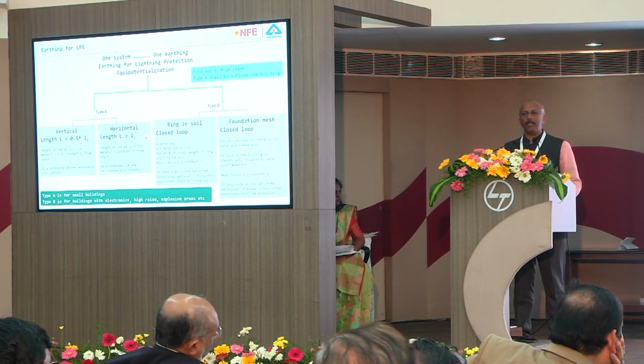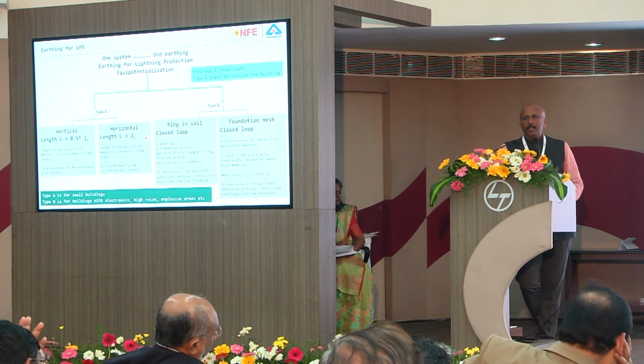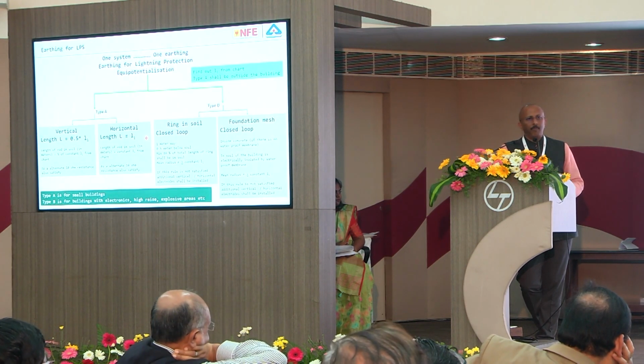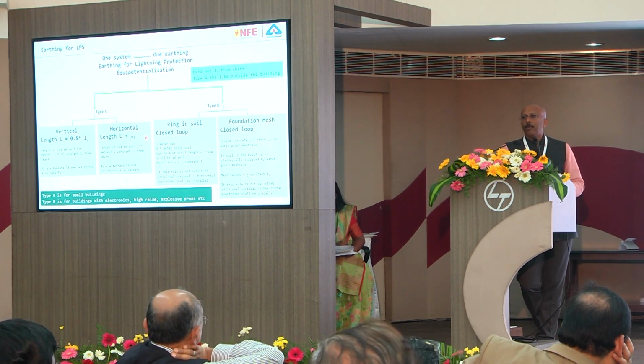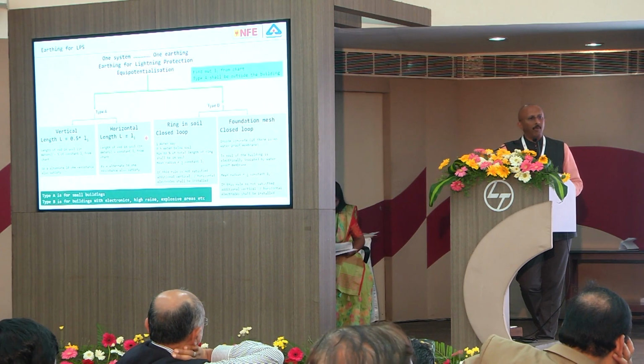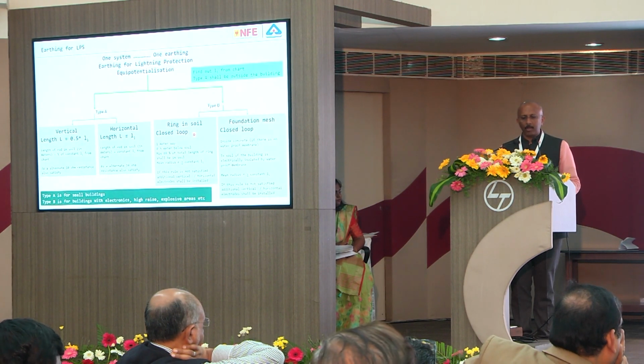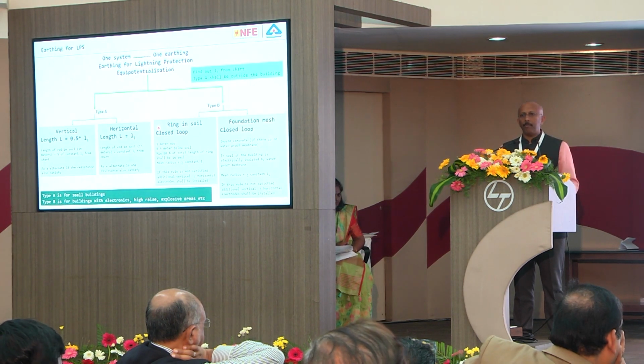So these four techniques can be used. Out of these four techniques, type A you can use for a normal building, for example a house. Whereas for a place where a lot of electronics is involved, you need to go for a type B earthing, or the last one, foundation mesh as a closed loop, ring or closed loop. This is also written in the standard. If you have an electronic installation, you go for a type B earthing.